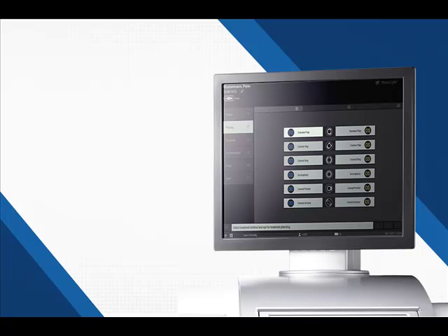What does flat dock look like? It should look like a series of parallel lines. From the front to the back of the cornea, through to the anterior capsule to the posterior capsule, it should all look like parallel lines. What does poor docking look like? That would be part of the eye where you could see the white of the sclera, the other part you couldn't. On the OCT imaging system, you would see a mountain peak in some area of the screen.